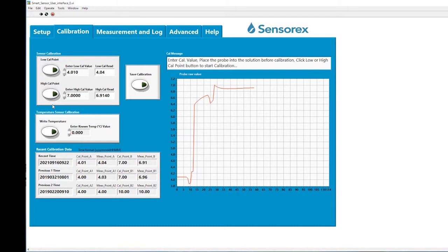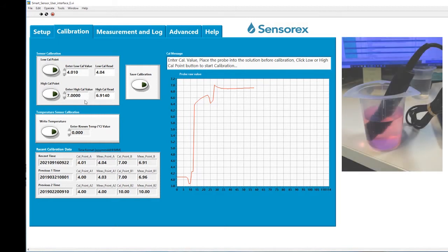In the case of today, we're going to go ahead and use pH 4.01 buffer for the low point and 7.00 buffer as your high calibration point. So let's start the process. I'm now placing the sensor into the pH 4.01 buffer. And the first thing I'm going to do is press the low point cal button.